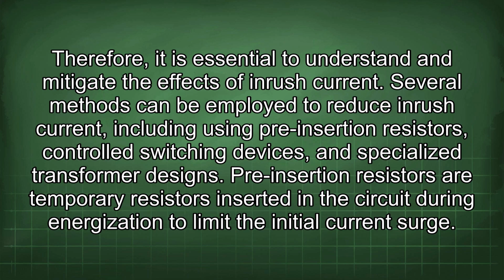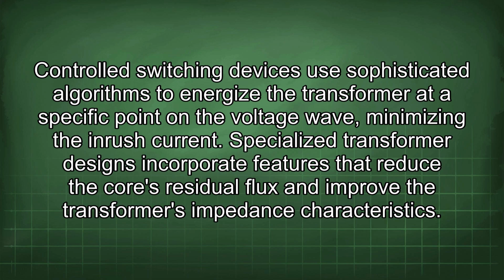Several methods can be employed to reduce inrush current, including using pre-insertion resistors, controlled switching devices, and specialized transformer designs. Pre-insertion resistors are temporary resistors inserted in the circuit during energization to limit the initial current surge. Controlled switching devices use sophisticated algorithms to energize the transformer at a specific point on the voltage wave, minimizing the inrush current. Specialized transformer designs incorporate features that reduce the core's residual flux and improve the transformer's impedance characteristics.